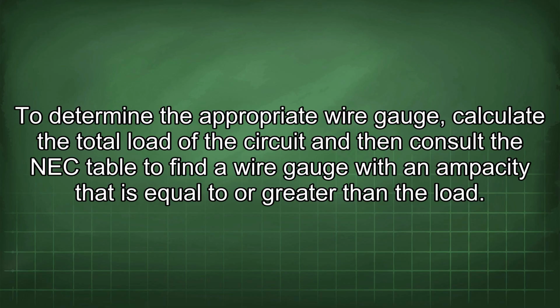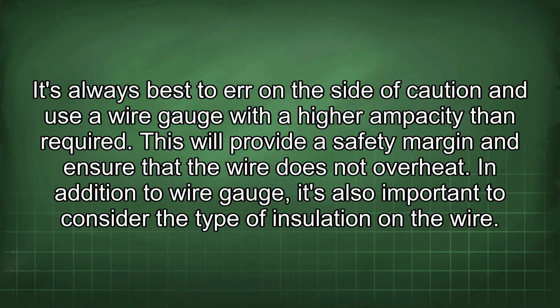To determine the appropriate wire gauge, calculate the total load of the circuit and then consult the NEC table to find a wire gauge with an ampacity that is equal to or greater than the load. It's always best to err on the side of caution and use a wire gauge with a higher ampacity than required. This will provide a safety margin and ensure that the wire does not overheat.